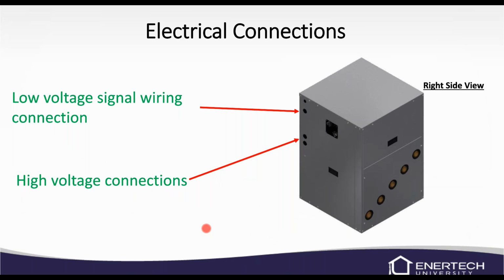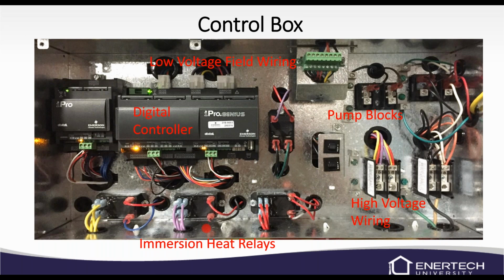Electrical connections, we have low voltage connections on the right and the left, so whichever works best for you. The high voltage is in the lower half, and the low voltage is in the upper corner there. This is the control box. So we've got our digital controller, we've got our iPro controllers. This is the removable terminal strip for the calls to the unit.